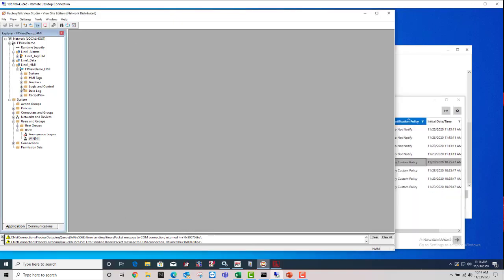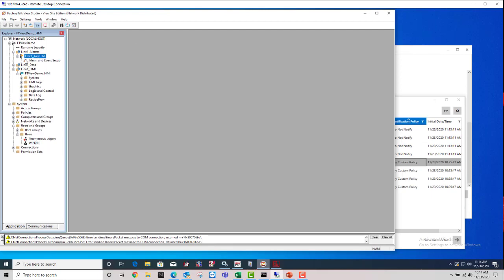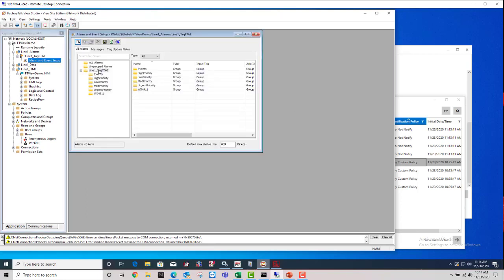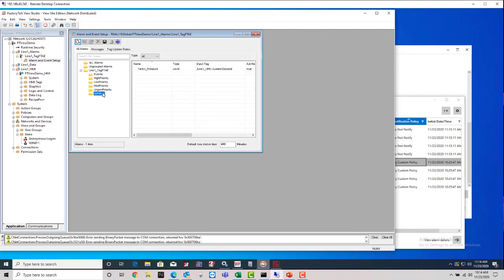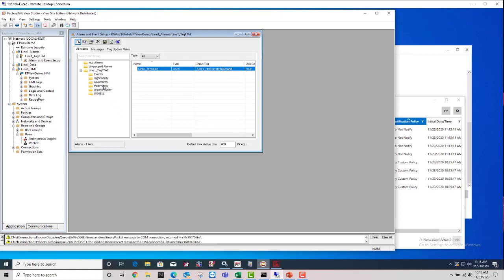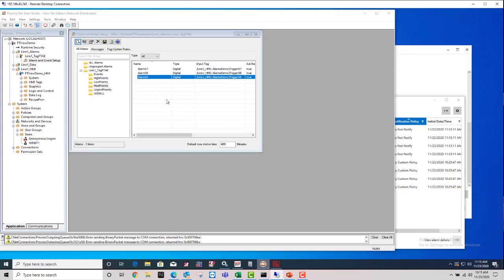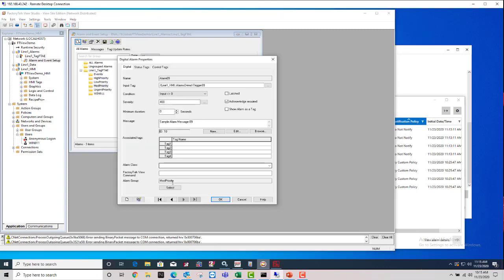All I did was open up my Factory Talk Alarm and Events server, and you can double-click that. I had gone in here and just right-click Add Group, and I made one called a Win911, and I assigned tank1 underscore pressure to it.